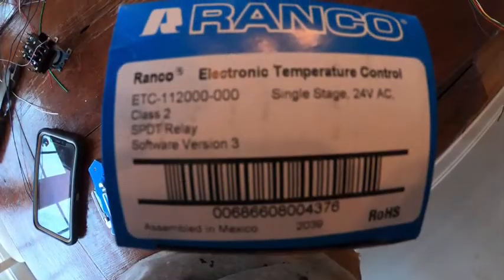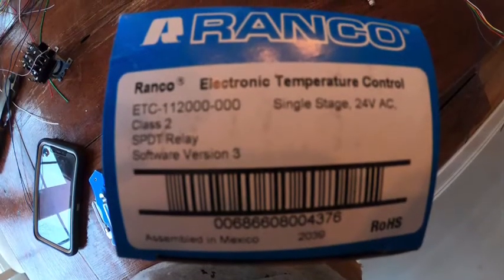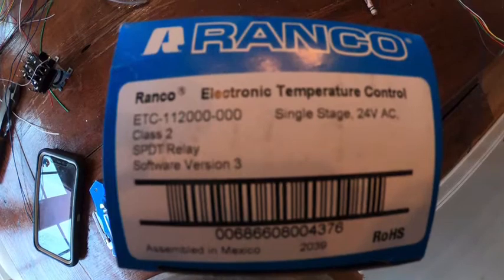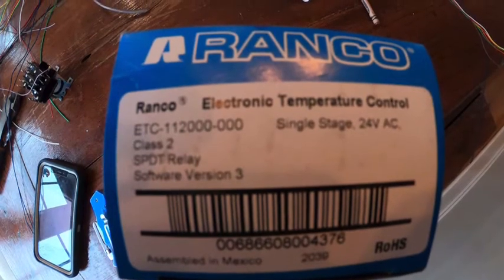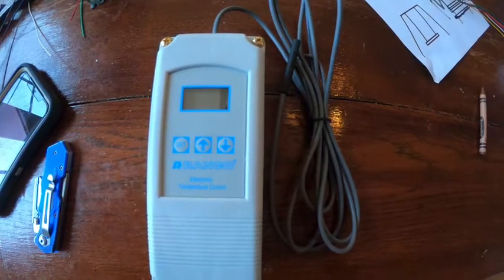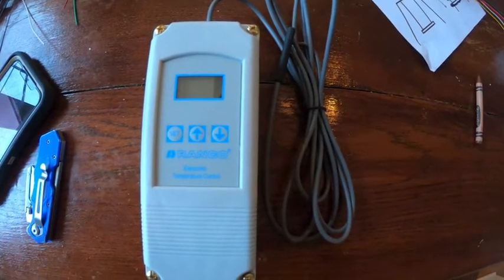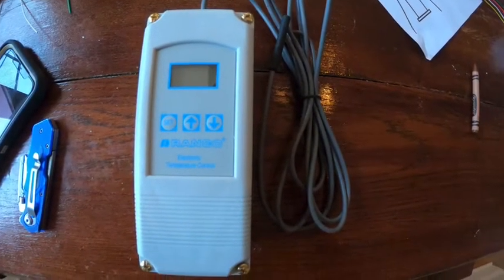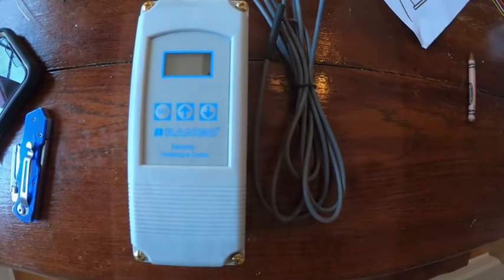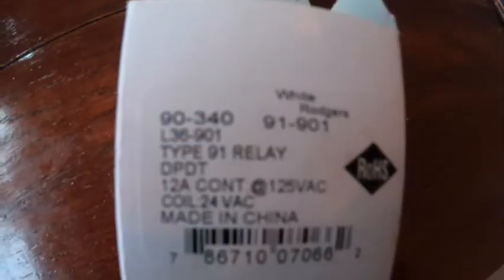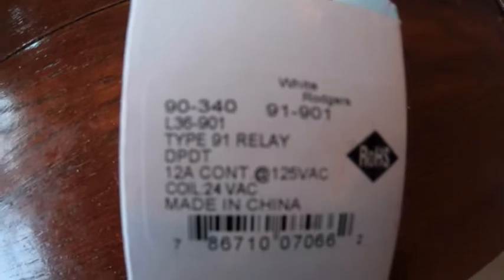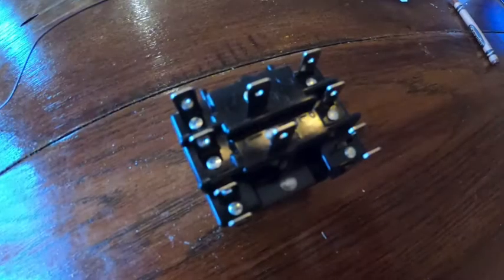One of the first things you'll need is a Ranco Aquastat. You're going to want the 24 volt version, not the 120. The part number is going to be ETC-112000-000. You'll also need a 90-340 type 91 relay.